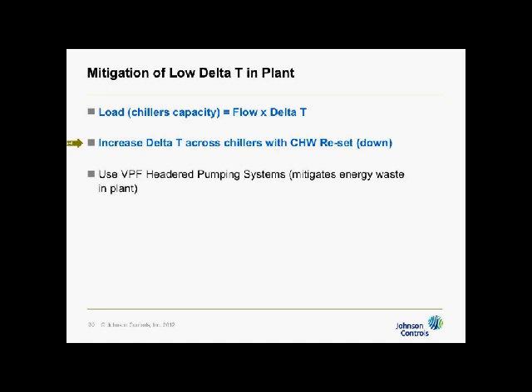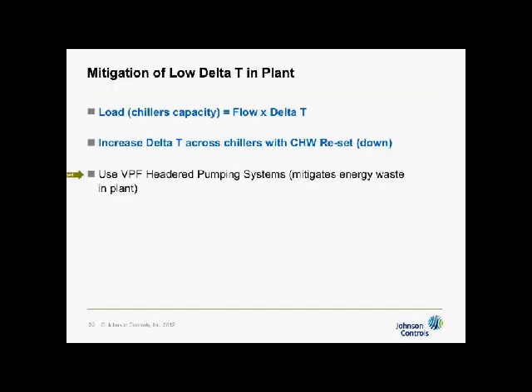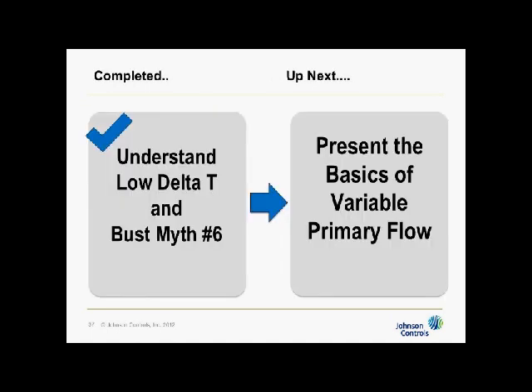The penalty to doing that is that the chiller's energy is going to go up roughly 1.5 to 2% per degree for 3 degrees. But it's still better than having to run more chillers than you need under conditions where you don't have optimal control on your auxiliaries. Right. Now, another way in which I can mitigate low delta T is that maybe I can find a way to do something about flow, because doing something about delta T has a negative impact from more energy on the chillers. But a VPF system is another solution because it provides me with an ability to also go above design flow. So that's low delta T, and we busted myth number 6.